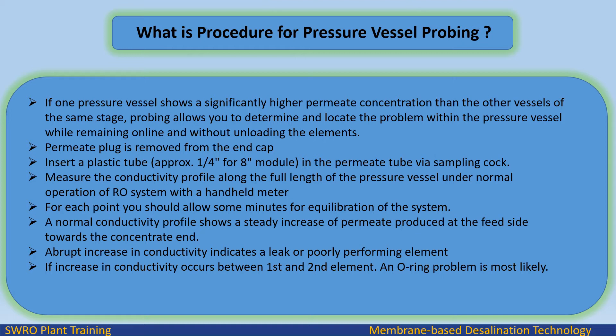The permeate plug is removed from the end cap. A plastic tube, approximately 1/4 inch, is inserted in the permeate tube via the sampling cock for an 8-inch module. The RO system is operated with a hand-held conductivity meter. For each measurement point, allow some minutes for equilibration. A normal conductivity profile shows a steady increase from the feed side toward the concentrate end, and an abrupt increase in conductivity indicates a leak or poorly performing element.